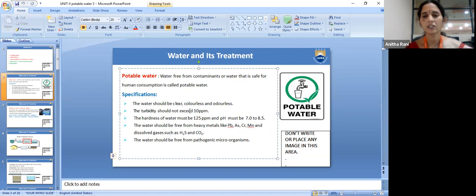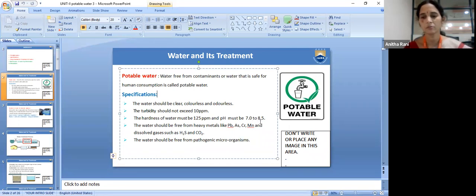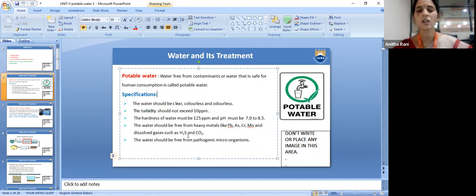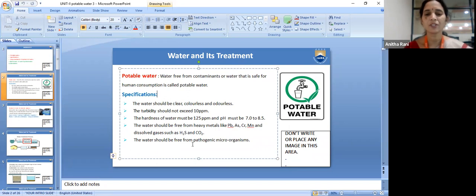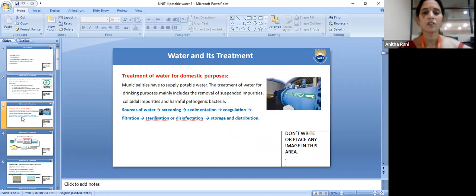Specifications of potable water: the water should be clear, colorless, and odorless. The turbidity should not exceed 10 ppm — turbidity means clay or mud particles. The hardness must not exceed 125 ppm. The pH must be 7.0 to 8.5, not more alkaline or more acidic. The water should be free from heavy metals like lead, arsenic, chromium, manganese, and dissolved gases such as H₂S and CO₂. The water should be free from pathogenic microorganisms.